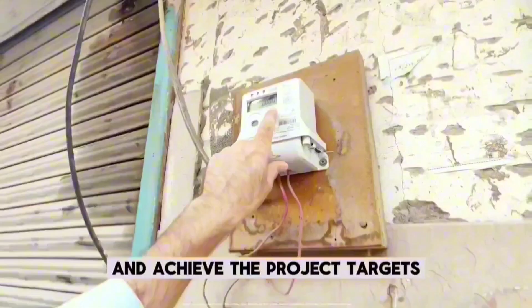The AMI meters having a PLC module basically operate on a neutral and a phase. In single phase, it is L1 and neutral, and in 3-phase, it is L3 and neutral. So, generally, communication works over two wires: one is neutral, another is phase. If two transformers have a common neutral, then the AMI meters will have two paths for communication. Maybe one through transformer T1 and another through transformer T2.